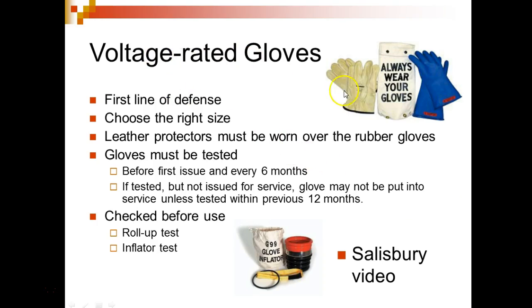Then they get into voltage rated gloves. First line of defense, choose the right size. Leather gloves protect the rubber gloves. And it says gloves must be tested what? You're supposed to have them tested every what? 6 months, yeah. If tested but not issued for service, glove may not be put into service unless tested within previous 12 months. So if you buy gloves and you put them on a shelf, you're still supposed to have them tested every what? Every 12 months. If you wear them, you're supposed to have them tested every 6 months.